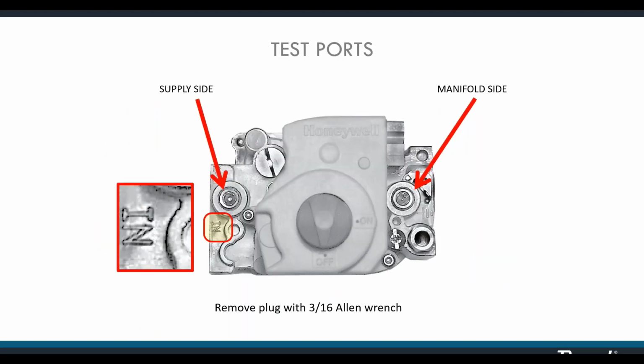The test ports are located on the gas valve, one on the supply side, one on the manifold side. The Allen wrench necessary for removing the plugs is often included with the manometer. If it is not, make sure you have a 3/16 inch Allen wrench in your toolbox. That's pretty standard across most swimming pool heaters, and most gas burning appliances of this nature will have similar test ports at a similar size.